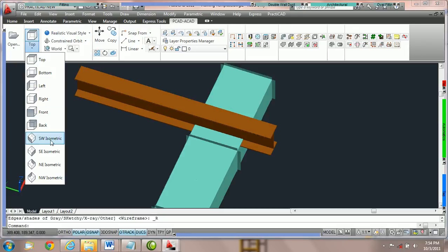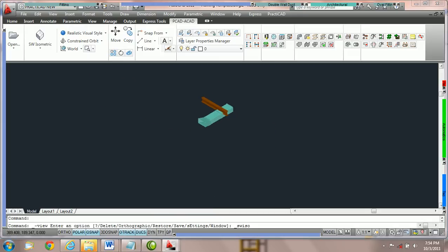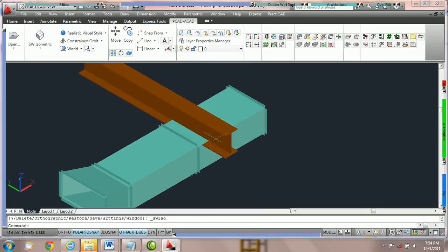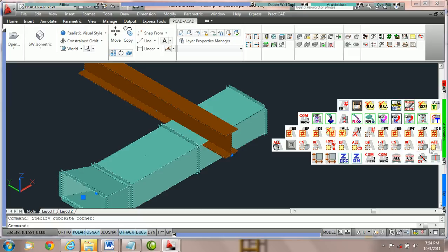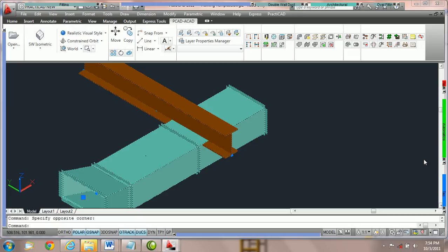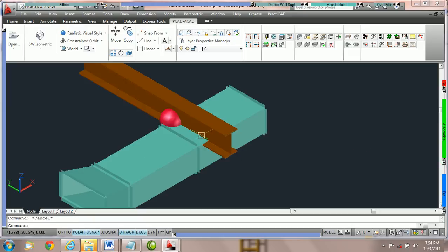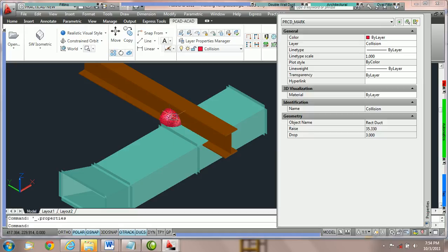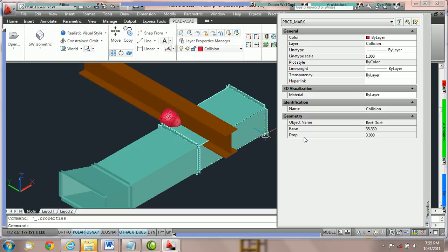We're going to put this in isometric view, zoom in a little bit, and run a Practicad collision detection automatic to see what type of change we need to make. I'm going to click on the collision ball, and here you can see it's telling us to drop down three inches to dodge this beam.